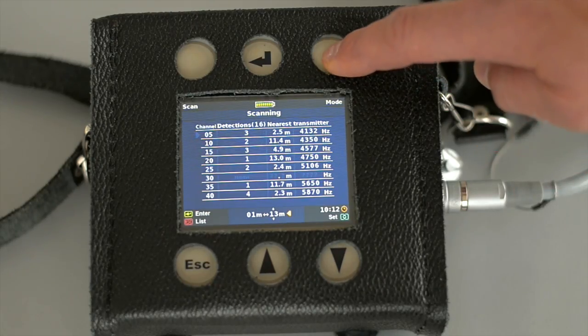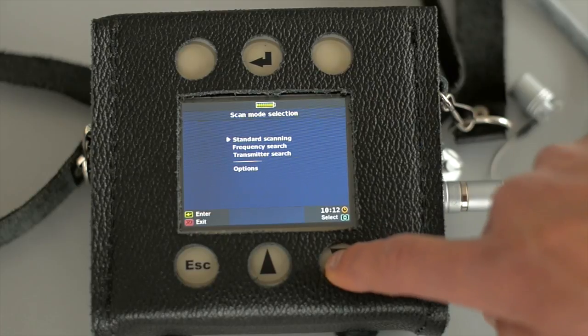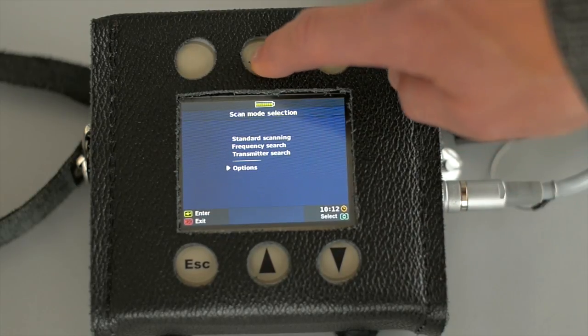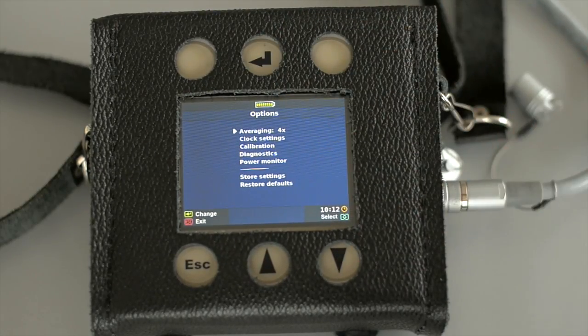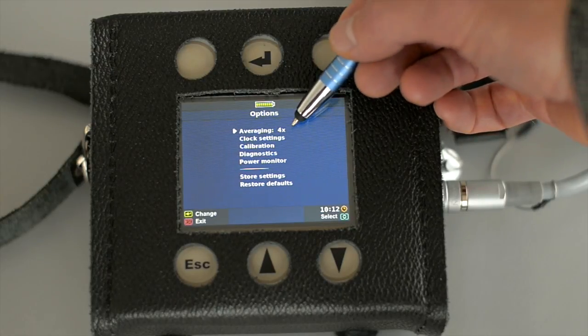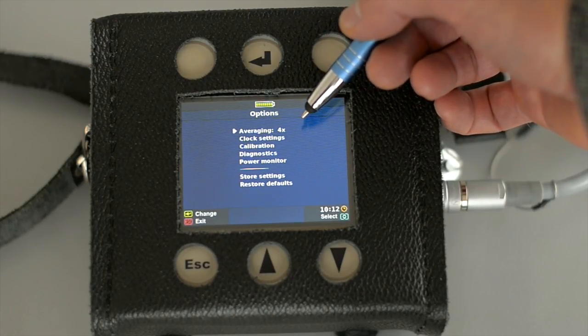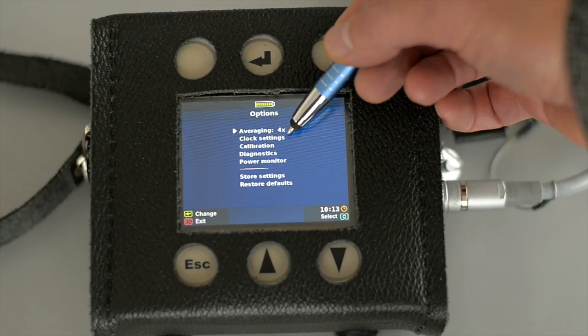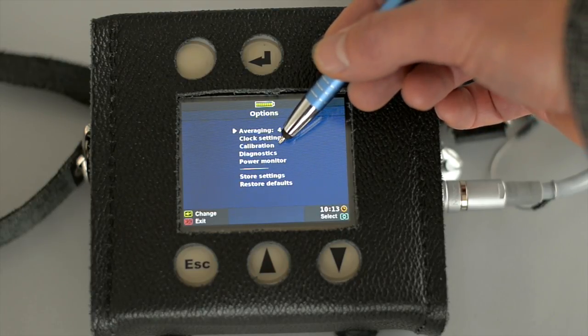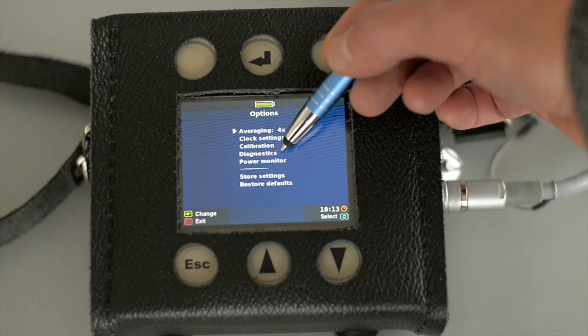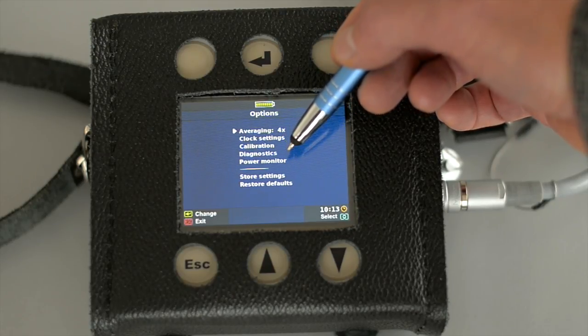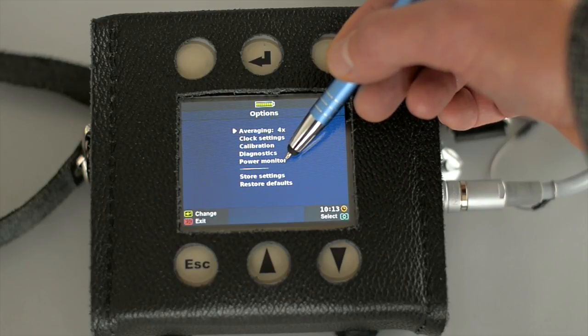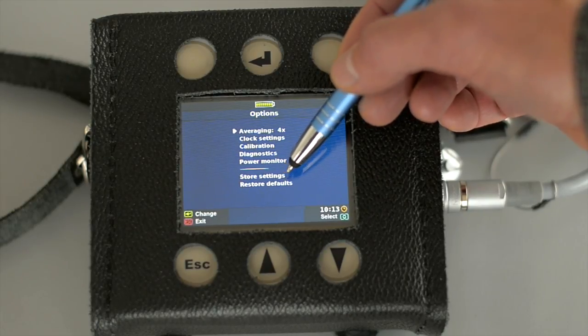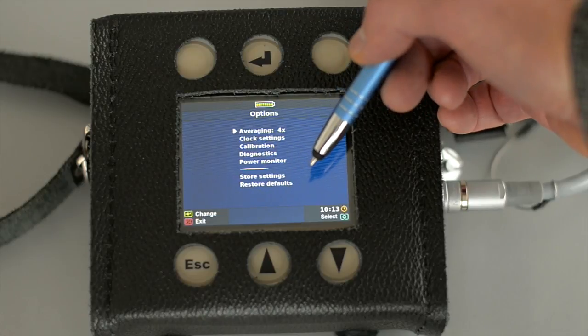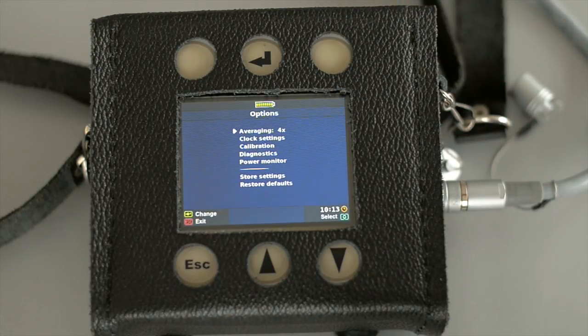We press the Mode key and then choose Options. The Options menu allows us to select the averaging level, set the clock, calibrate, perform diagnostics, and monitor the power status of the central unit. We select the desired option using the up and down arrow keys and pressing the Enter key, while the option is marked with a triangle on the left side. The settings can be stored and restored from the memory.